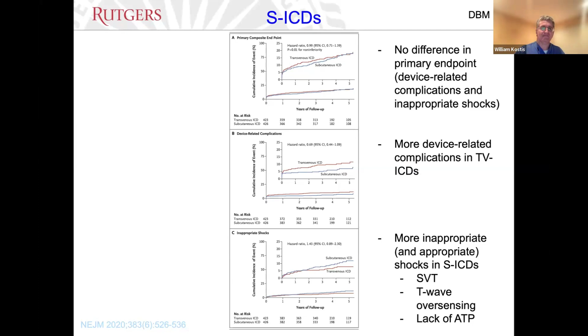In other words, the sub-Q ICD achieved what it intended to do, which is to say we're going to have fewer infections, we're going to have fewer vascular problems with this system. However, the trade-off is there were a lot more inappropriate shocks in the sub-Q ICD group. This is because sometimes people would get inappropriate shocks for supraventricular tachycardia or when there was T-wave oversensing leading to double counting of the rate. And also appropriate shocks were more common because since these devices can't provide ATP, the only thing they could do to terminate VT was a shock.